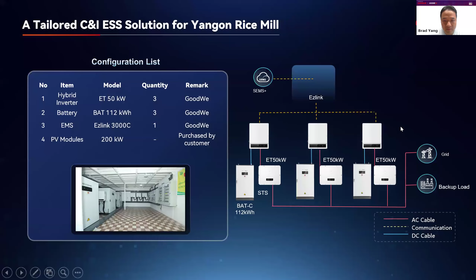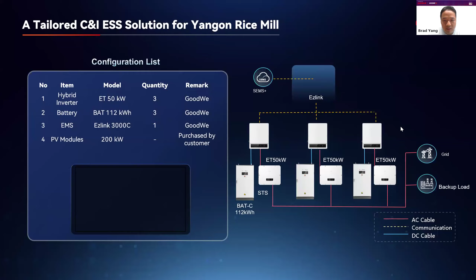Next up is our custom C&I energy storage system solution for this Yangon rice mill. We have configured 3 pieces of 50 kilowatt hybrid inverters and 3 pieces of 112 kilowatt hour batteries. As shown in this diagram, the system connects to the grid, the mill's backup loads, and the batteries, with the EMS managing everything and linking to our SEMS Plus cloud for remote monitoring and configuration. This setup is perfectly matched to the mill's 100 to 120 kW load, enabling production to run 24 hours, 7 days a week, while cutting costs.